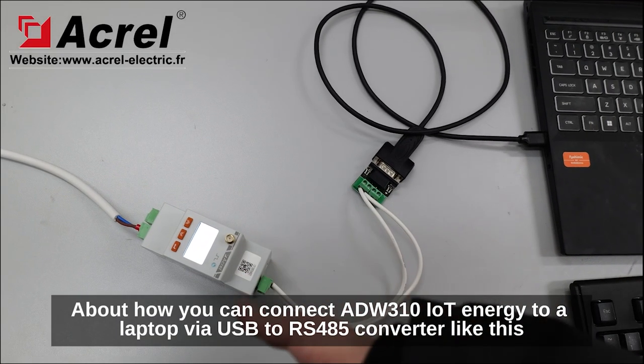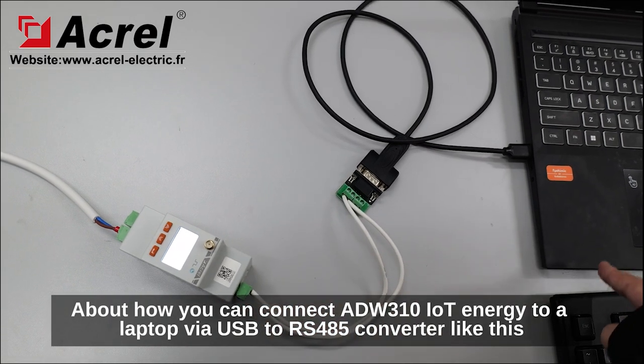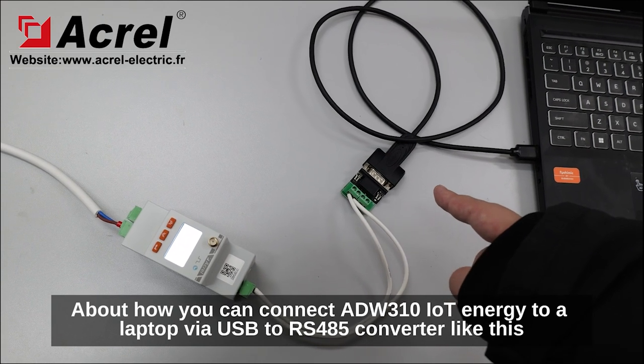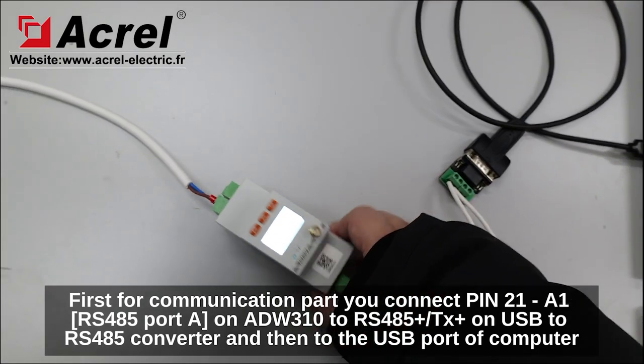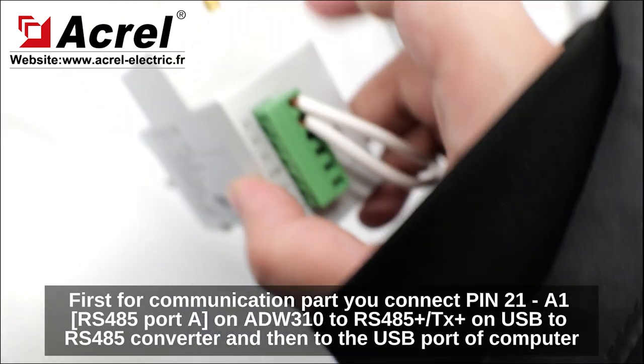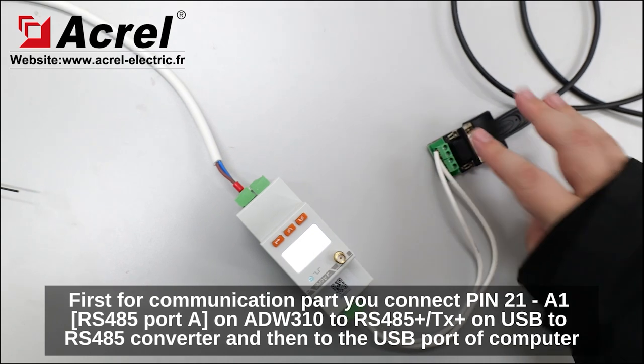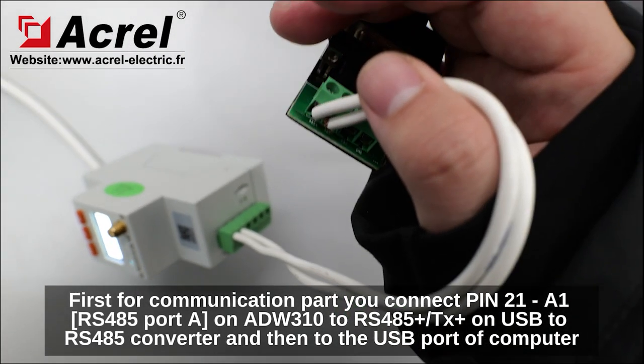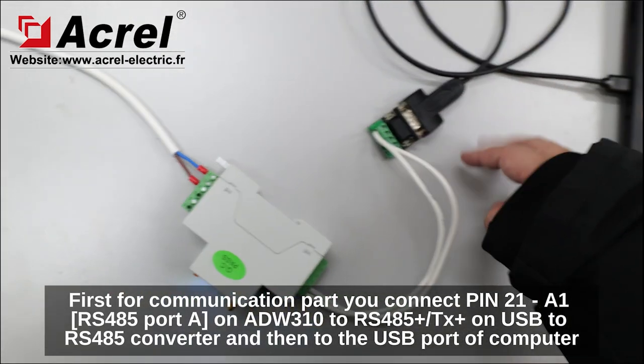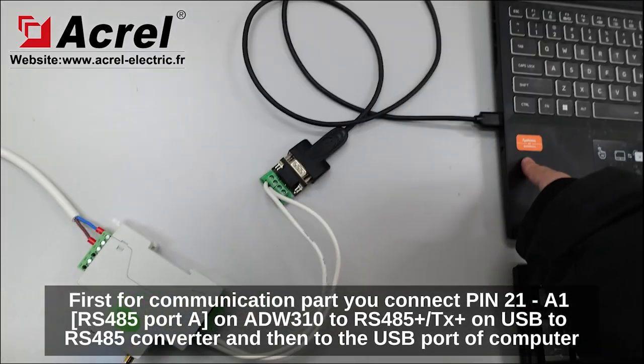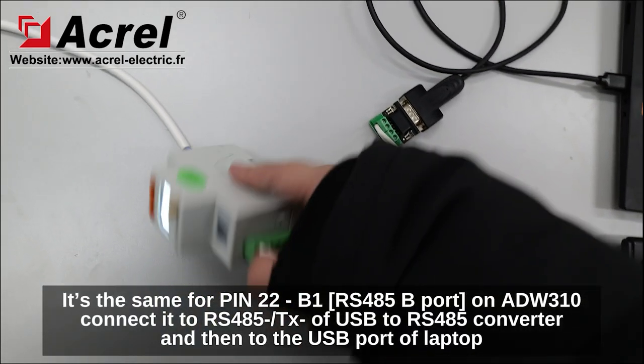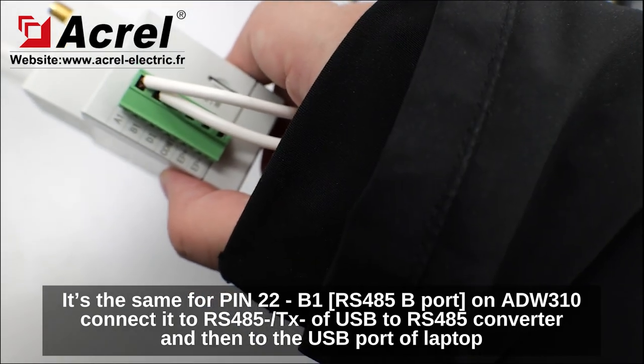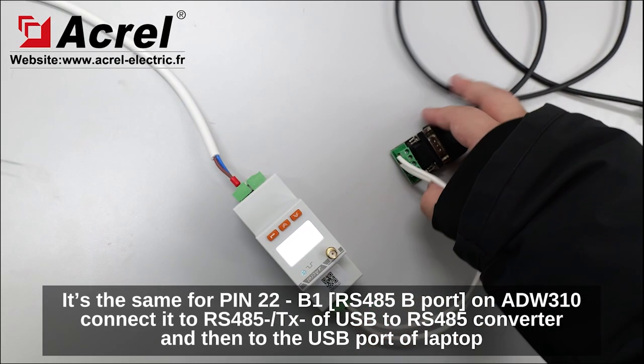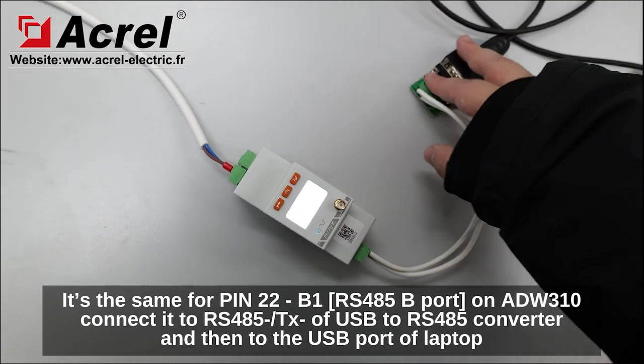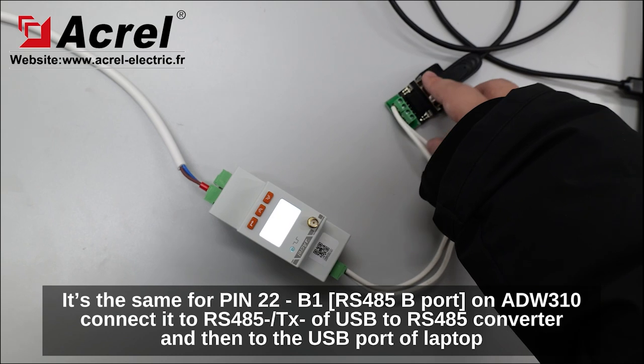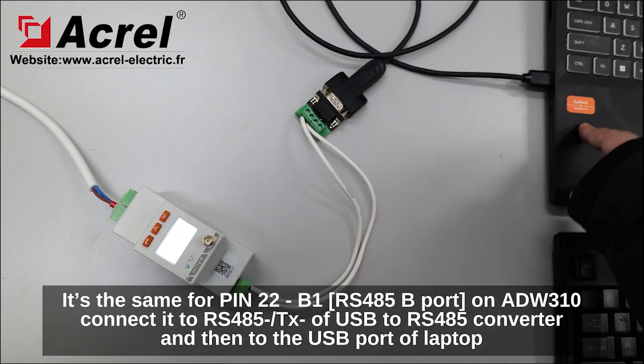About how you can connect an ADW310 IoT energy meter to a laptop via USB to RS485 converter like this. First, for the communication part, you connect pin 21 A1 on ADW310 to RS485 plus or TX plus on the USB to RS485 converter and then to the USB port of the computer. It's the same for pin 22 B1 on ADW310: connect it to RS485 minus or TX minus of the USB to RS485 converter and then to the USB port of the laptop.